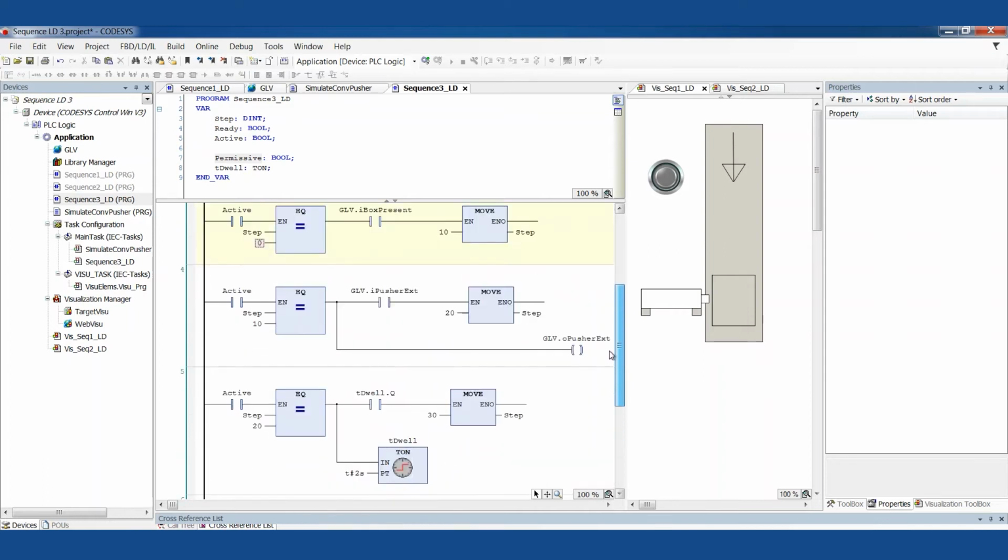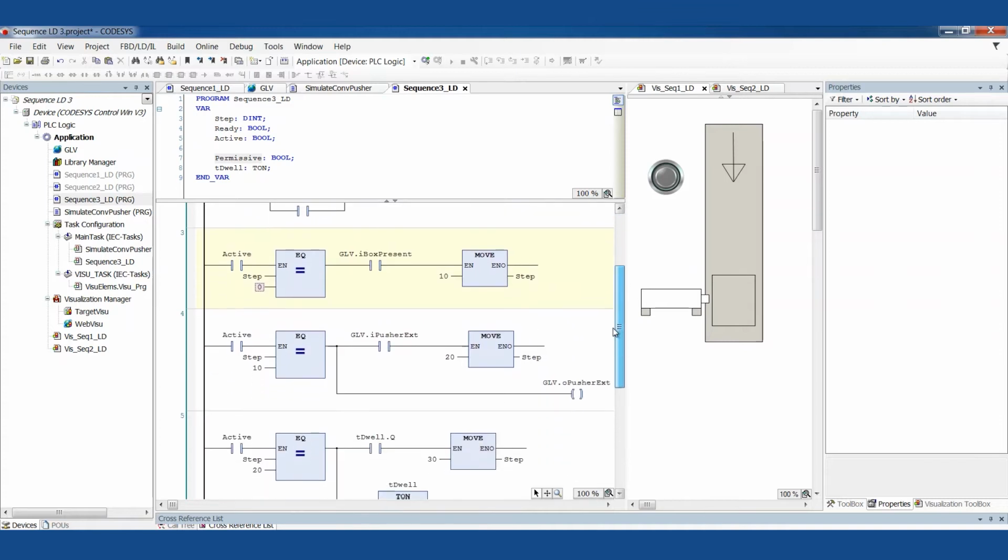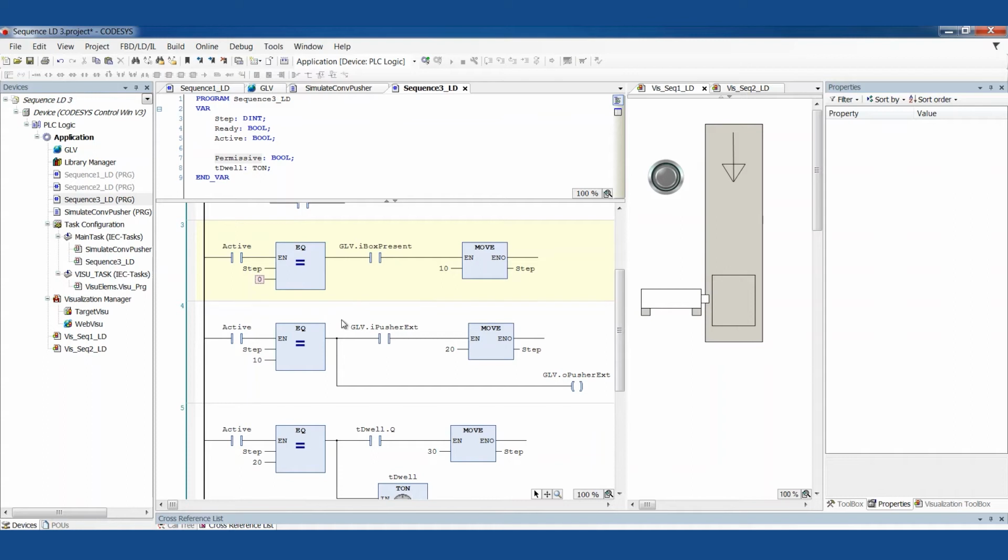Now, why am I counting up by tens? Well, it's nice to have a space in case you decide you need an intermediate step. I can put 9 intermediate steps here. So plenty of room for expansion and growth and filling in blank spaces where I forgot to put something. To be honest with you, I'm OCD enough that after I've gone through a project and I've debugged it and started it up, and I may have some 5s and 7s and whatever in here, I usually do go back and set it all to 10s again. And that may just be because I'm OCD. I think it makes it look a little prettier for the next guy. It looks like a complete product that way rather than looking like something that's already gone through the maintenance cycle a few times. But it's not necessary at all.